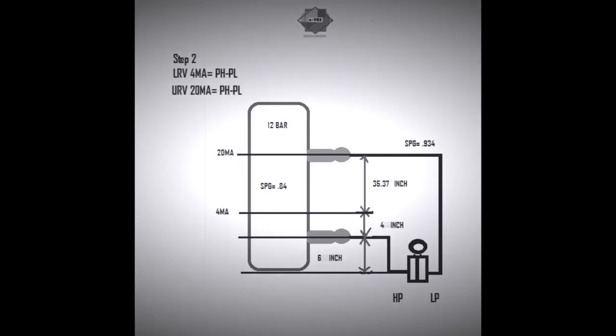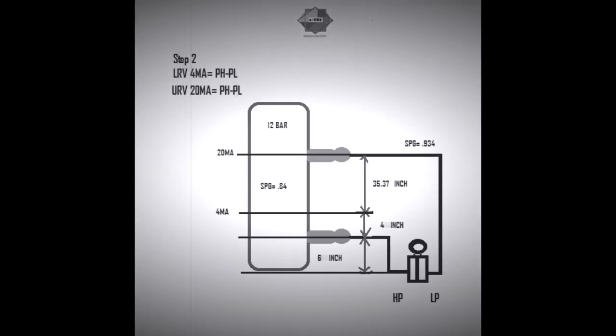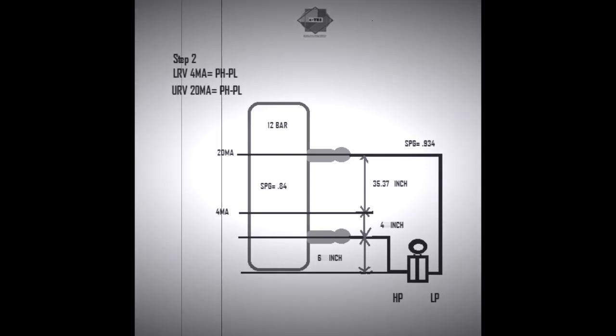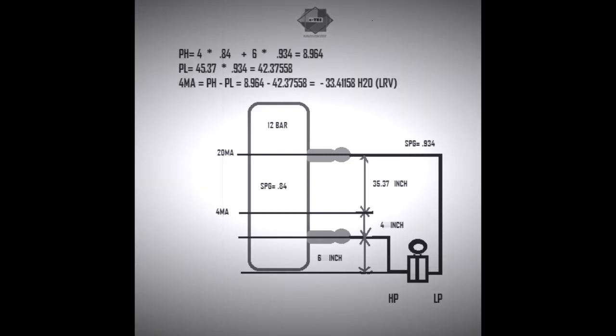For LRV, the formula is PH minus PL. PH is calculated as: the 4-inch zero percentage level above HP tapping, that is 4 inches multiplied by process gas specific gravity 0.84, plus the 6 inches below the HP side tapping point where the transmitter is mounted, multiplied by the capillary specific gravity 0.934. We get PH = 8.964.